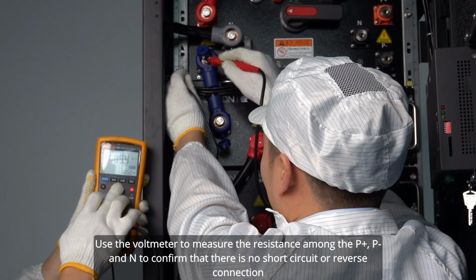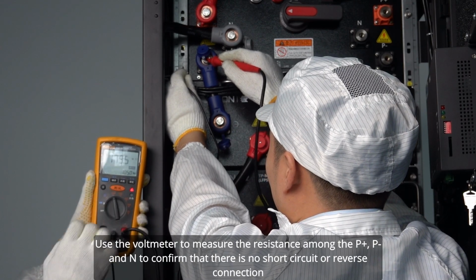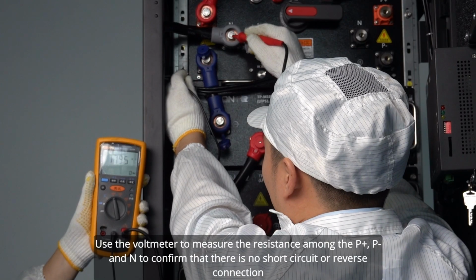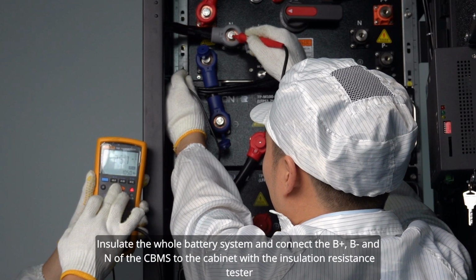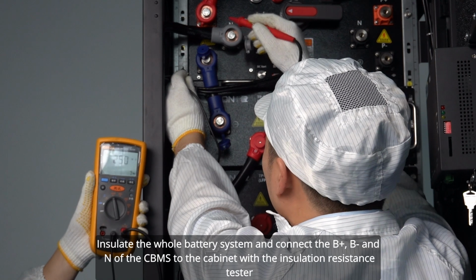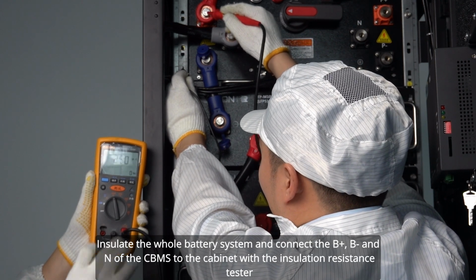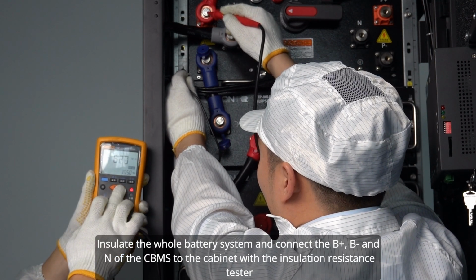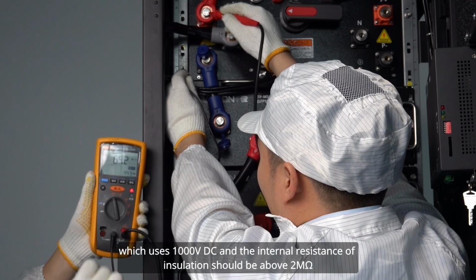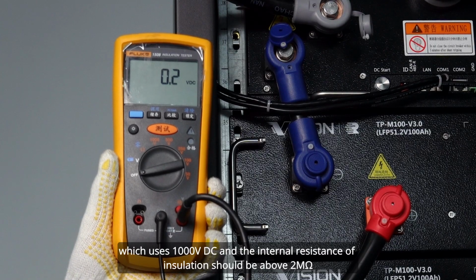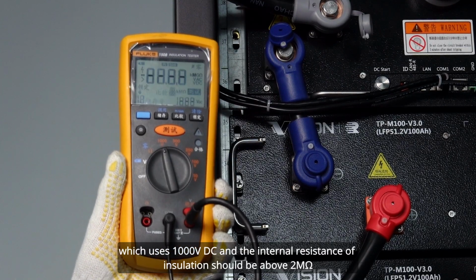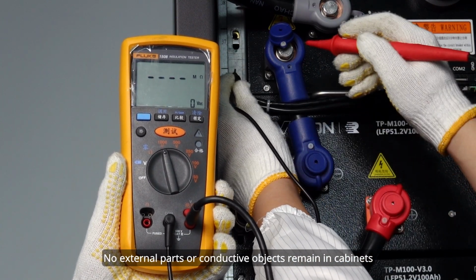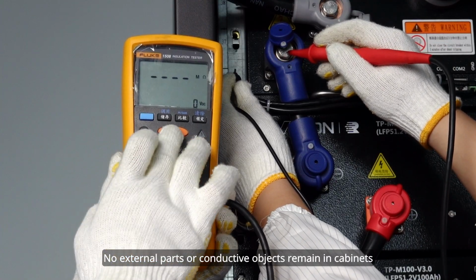Use the voltmeter to measure the resistance among the P+, P and N to confirm that there is no short circuit or reverse connection. Insulate the whole battery system and connect the B+, B and N of the CBMS to the cabinet with the insulation resistance tester, which uses 1000 VDC, and the internal resistance of insulation should be above 2 megaohms. No external parts or conductive objects remain in cabinets.